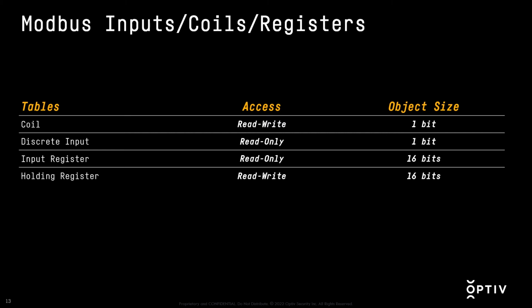To keep it as simple as possible, a coil is read-write—that's what controls things in physical space for the most part. Your switches are discrete inputs that tell the coil to initiate physical movement. You also have input and holding registers, where you can put variables, so you can see things like temperature and different types of measurements within those registers.